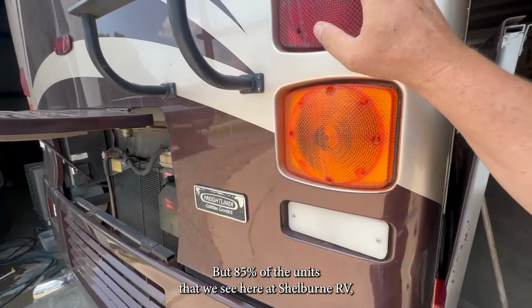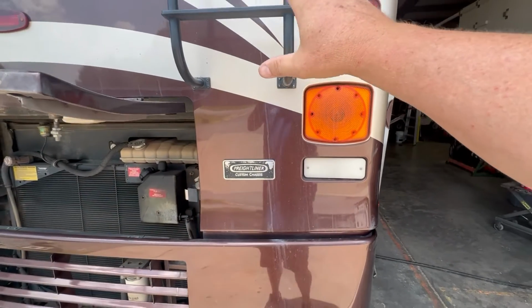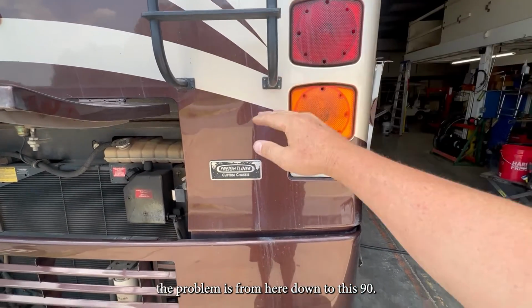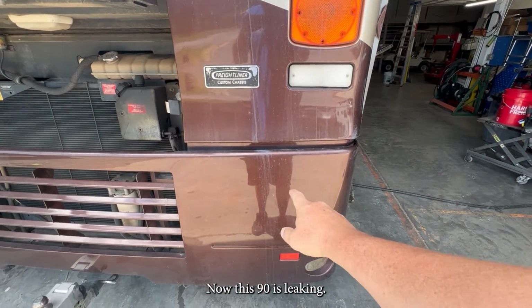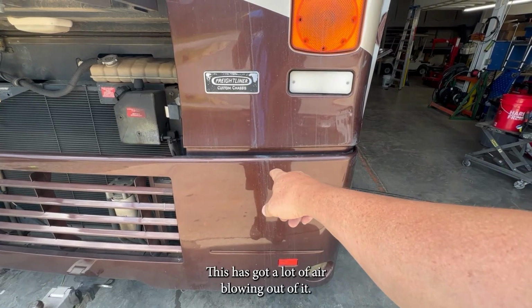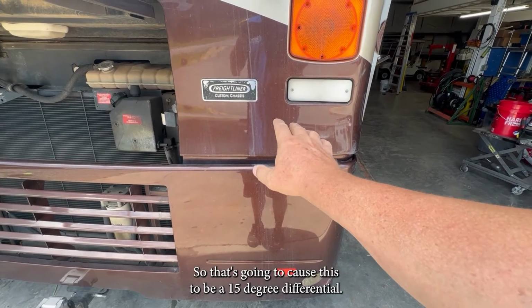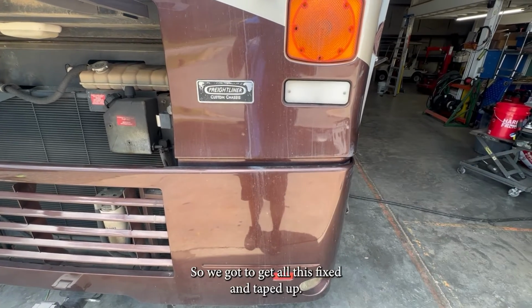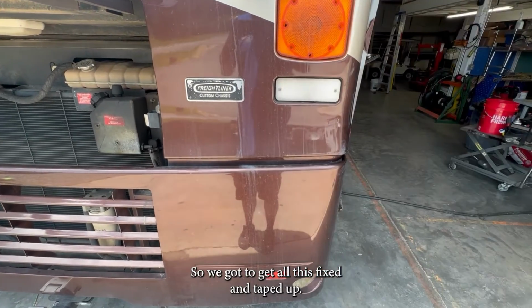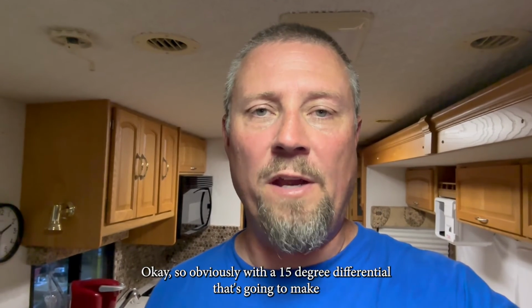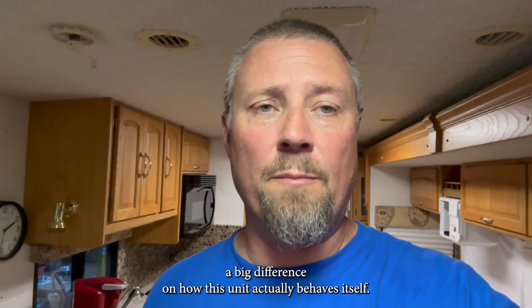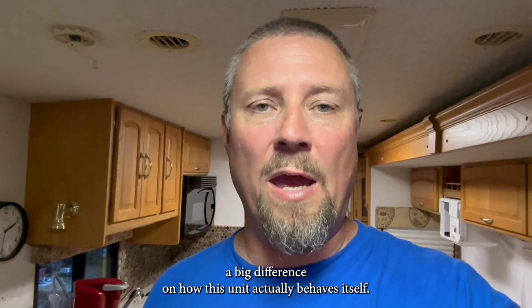But 85% of the units that we see here at Shelburne RV, the problem is from here down to this 90. Now this 90 is leaking. This has got a lot of air blowing out of it. So that's going to cause this to be a 15-degree differential. So we've got to get all this fixed and taped up. Obviously, with a 15-degree differential, that's going to make a big difference in how this unit actually behaves.